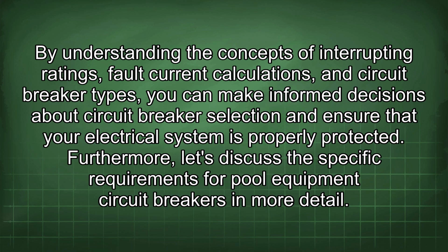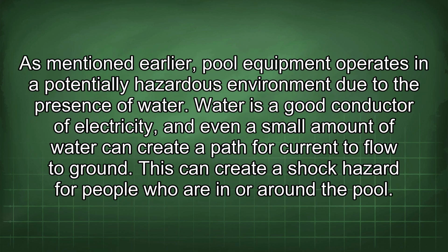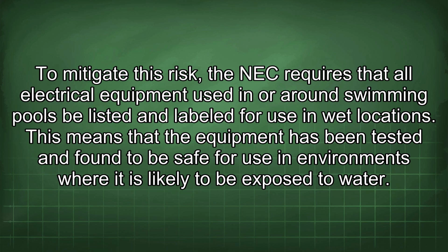Furthermore, let's discuss the specific requirements for pool equipment circuit breakers in more detail. As mentioned earlier, pool equipment operates in a potentially hazardous environment due to the presence of water. Water is a good conductor of electricity, and even a small amount of water can create a path for current to flow to ground. This can create a shock hazard for people who are in or around the pool. To mitigate this risk, the NEC requires that all electrical equipment used in or around swimming pools be listed and labeled for use in wet locations.